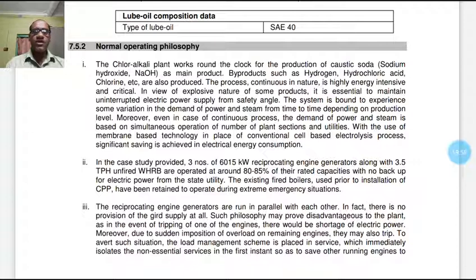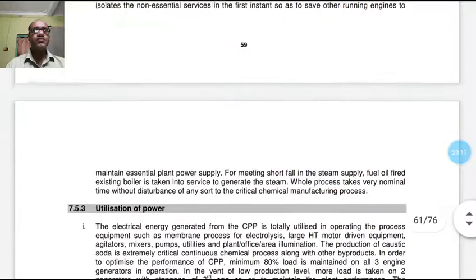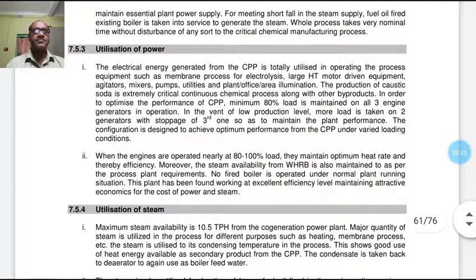To avert such a situation, the load management scheme is placed in service, which immediately isolates the non-essential services in the first instant so as to save other running engines and maintain essential plant power supply. For meeting shortfall in the steam supply, the fuel oil fired existing boiler is taken into service to generate steam. The whole process takes very nominal time without disturbance of any sort to the critical chemical manufacturing process.